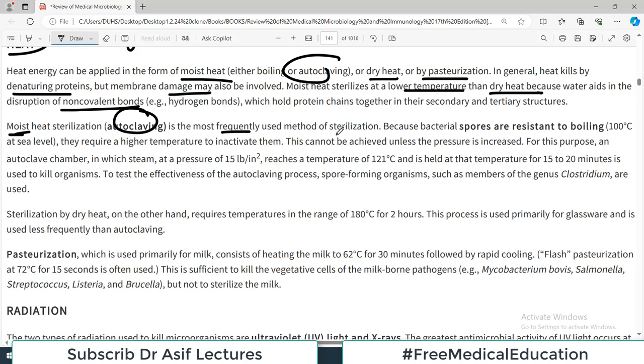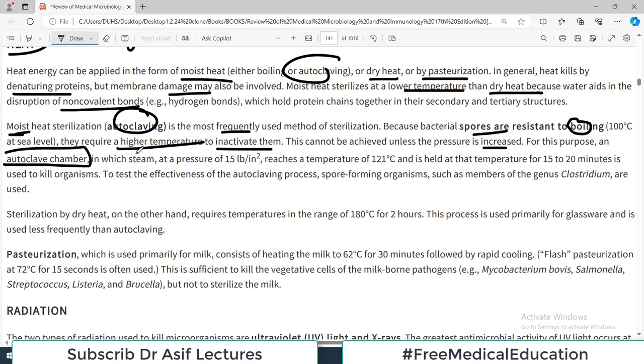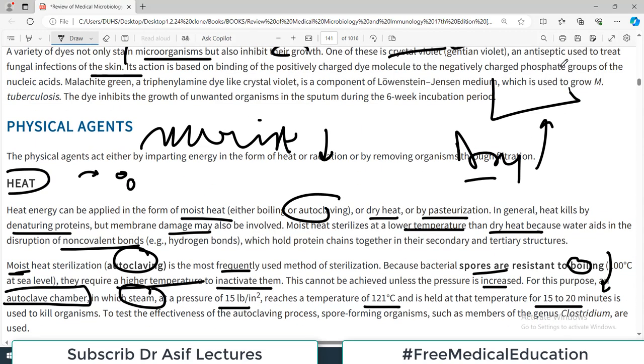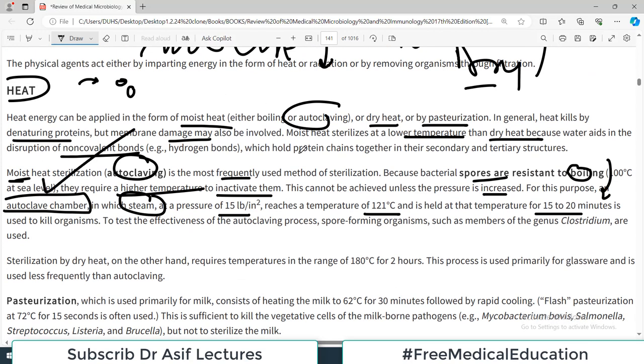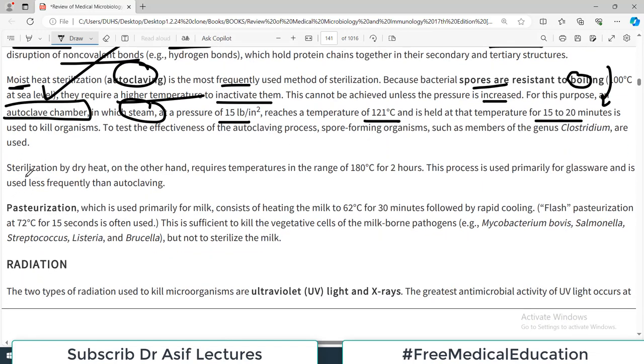Moist heat sterilization such as autoclaving is most frequently used in clinics and hospitals. Bacterial spores are resistant to boiling and require higher temperatures to inactivate them — this cannot be achieved unless pressure is increased. An autoclave chamber uses steam at very high pressure and temperature for 15 to 20 minutes. The machine runs at 121 degrees centigrade, 15 pounds per square inch pressure, for 15 minutes. This kills literally everything, including the spores.